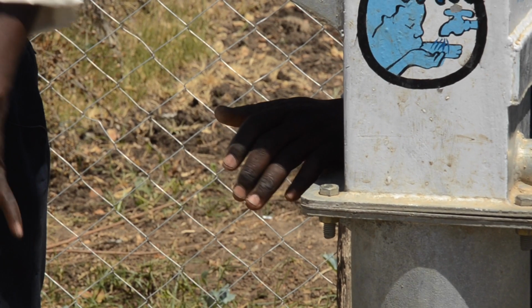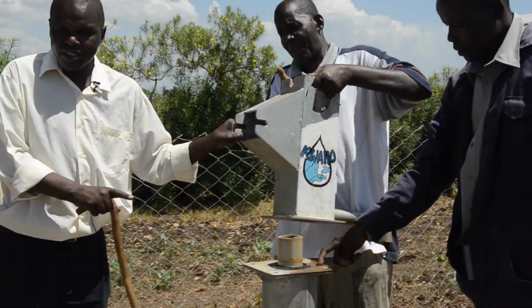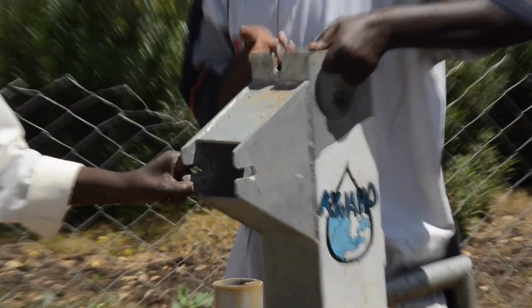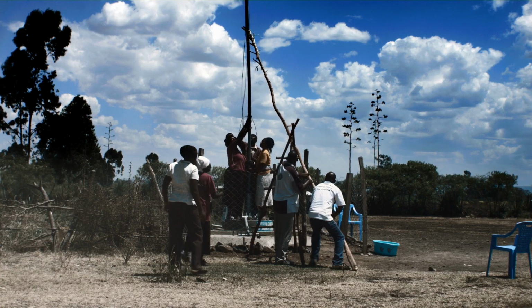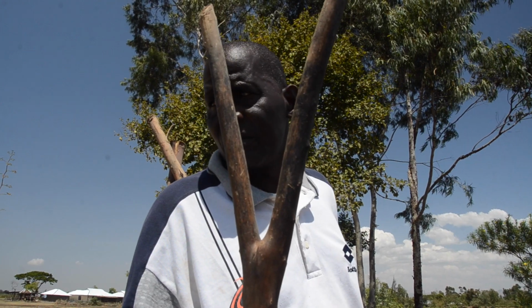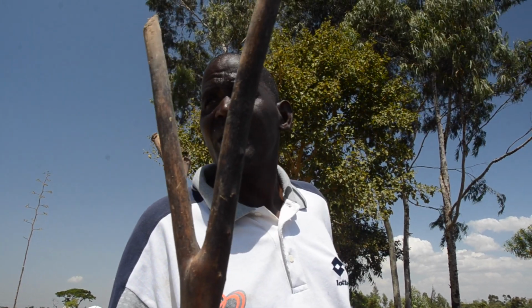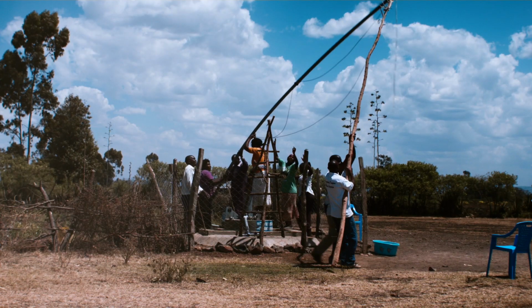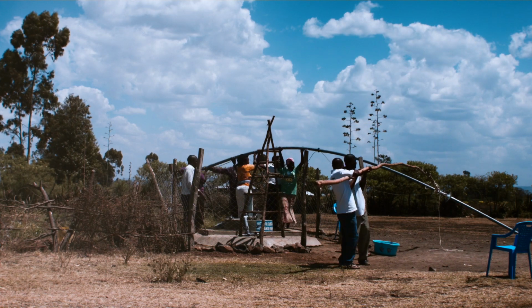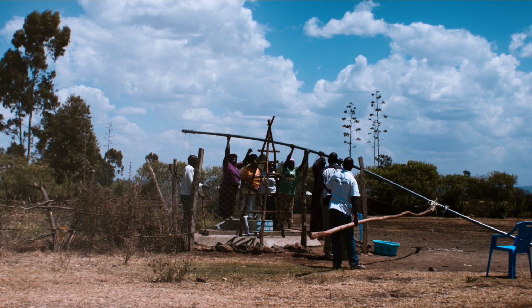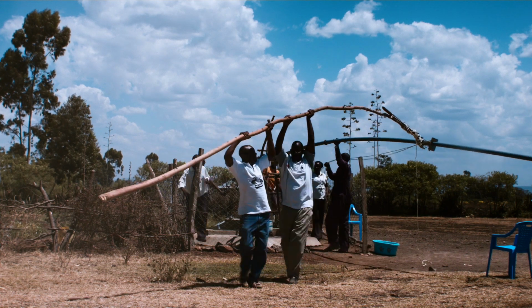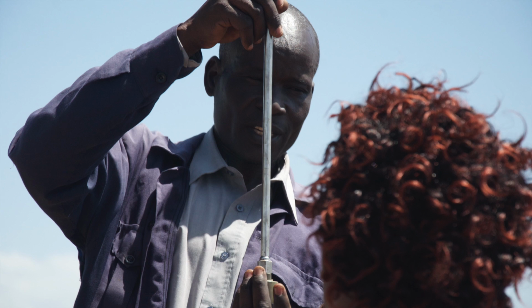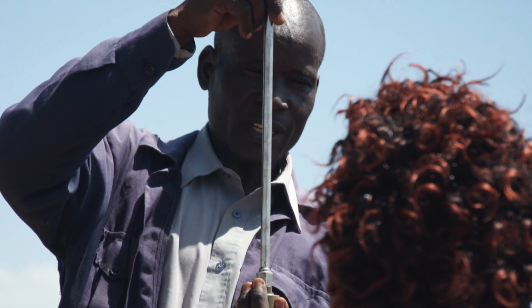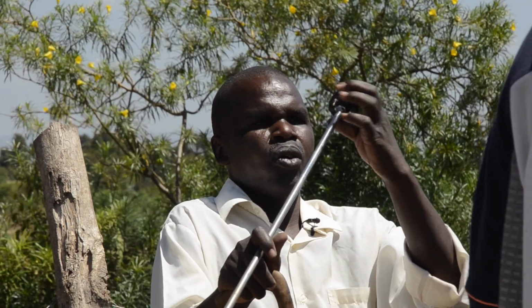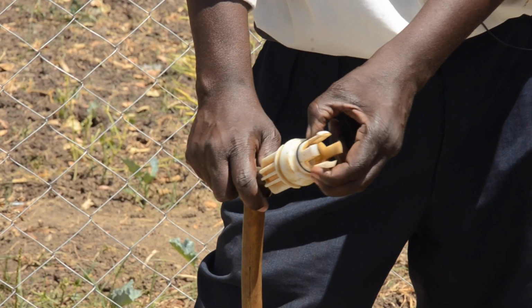In addition to the tools needed for pump repair, the additional resources needed to withdraw the raising main are at least 8 people, poles with forked ends for supporting the raising main when pulled out. A cleared area is required next to the well, long enough to accommodate the complete raising main when laid down immediately after withdrawal. You must examine all of the components of the pump, fix the breakdowns, and replace damaged parts such as centralizers, bobbins, and the seals.